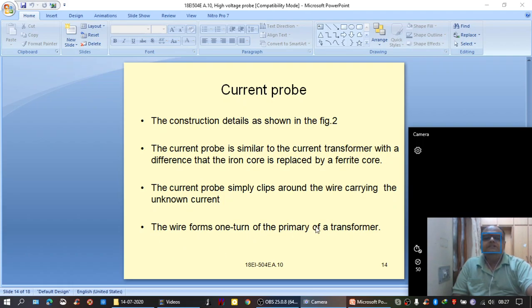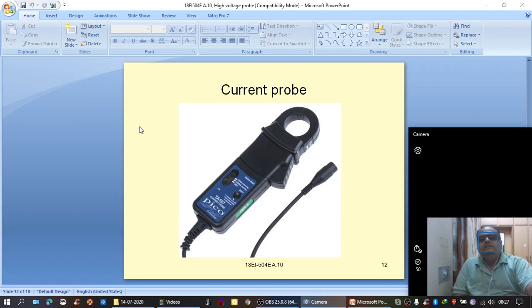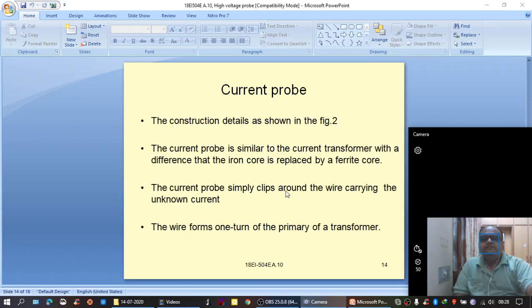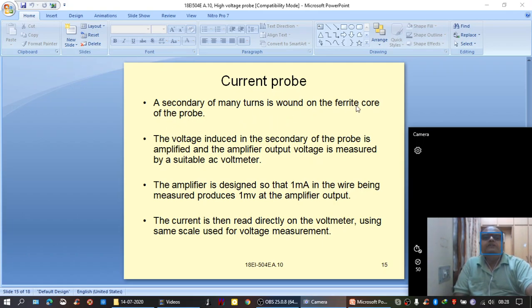The wire forms one turn of the primary of a transformer. As I told, it works on the principle of a transformer with this as primary, that is, the live current carrying wire placed within this hole acts as the primary, and then there would be a core on which a coil is wound that acts as the secondary. Due to electromagnetic induction, voltage would be generated in the secondary coil which is wound on the core, and that voltage is used for the measurement. A secondary of many turns is wound on the ferrite core of the probe.